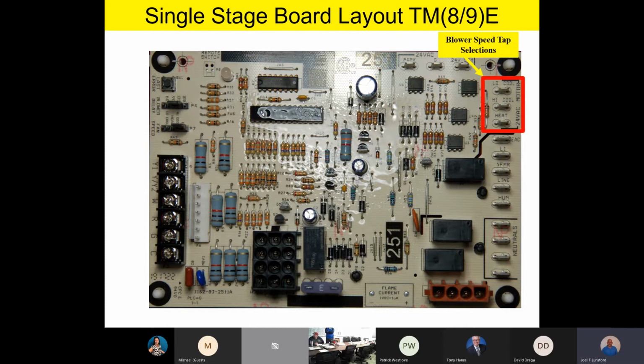As we move around the board, we also have some motor speed taps. We have low cooling speed, high cooling speed, and then our heating speed. So these speed taps, we'll have to select the proper speed taps based on our cooling airflow needs and our heating airflow needs based on our furnace, filtration, and ductwork and so on. So when we commission the unit, or when we install the unit, we have to make sure to select the proper speeds to give us the proper airflow.